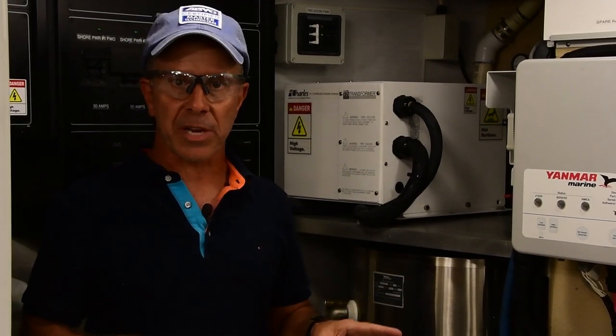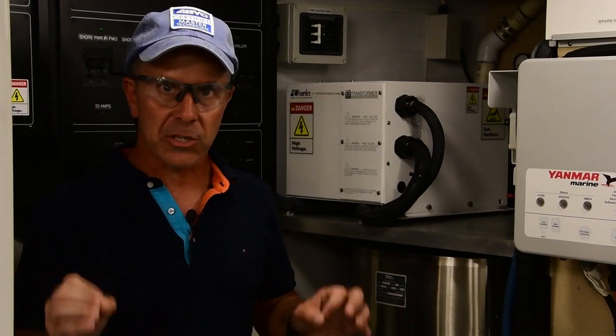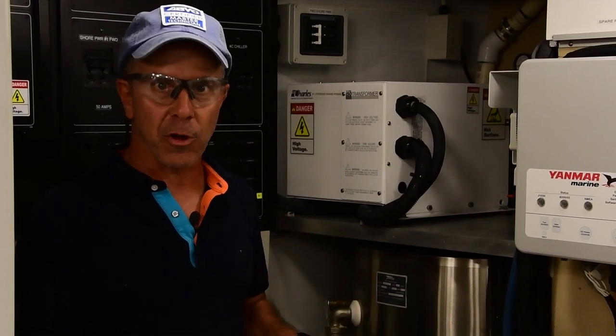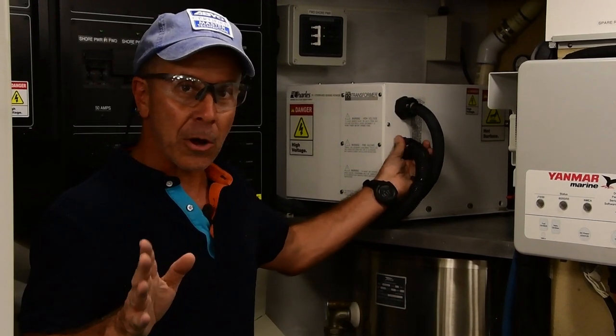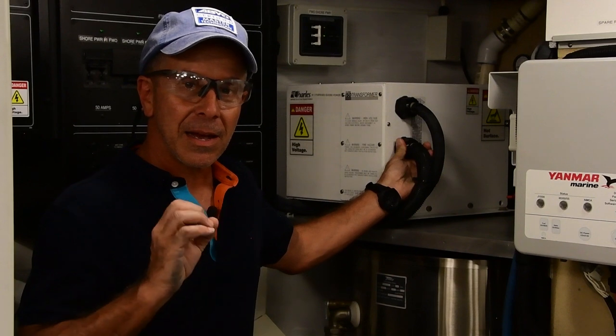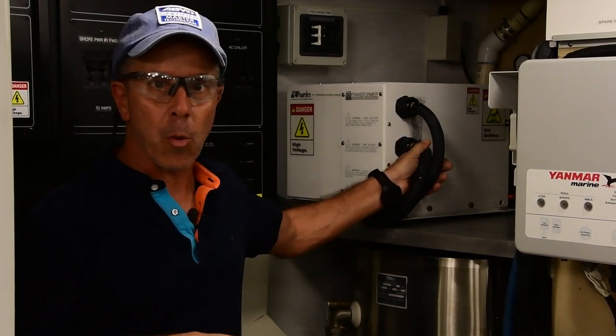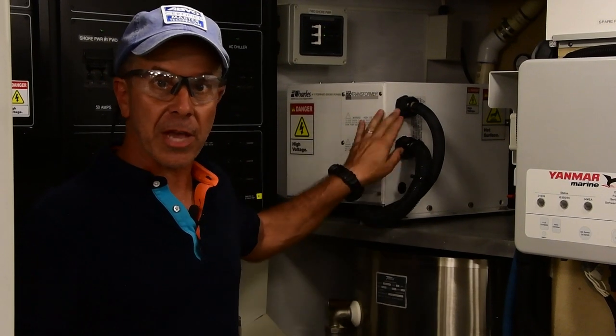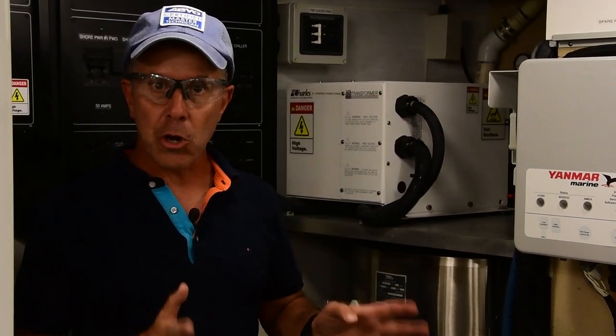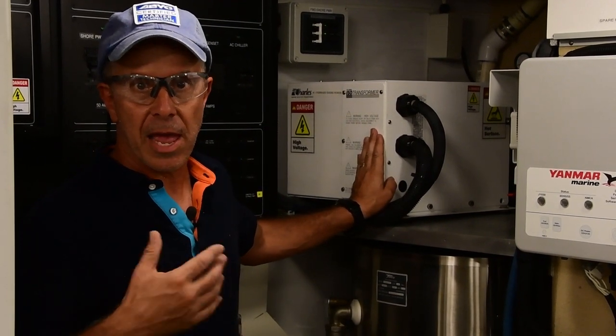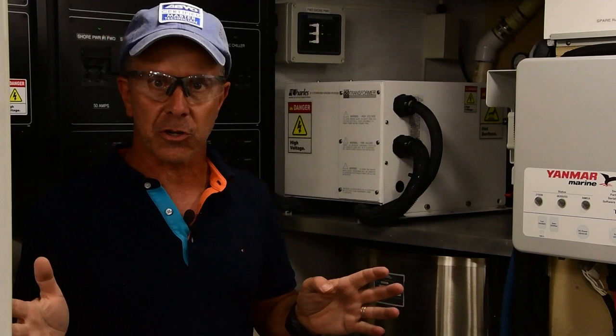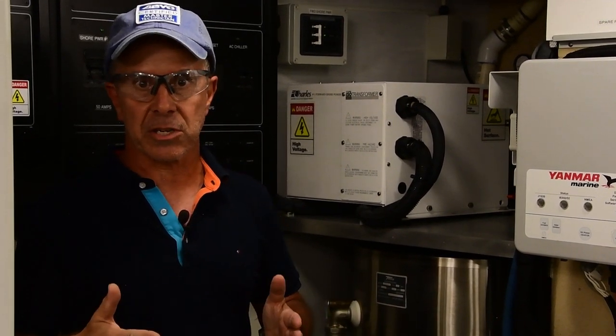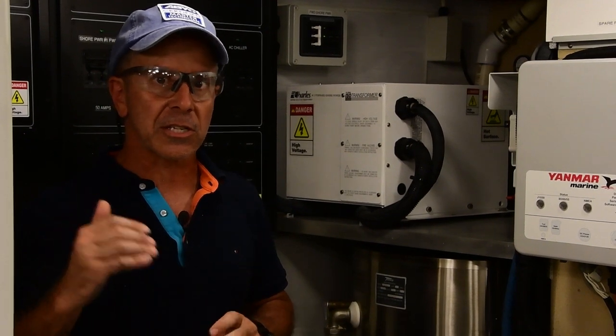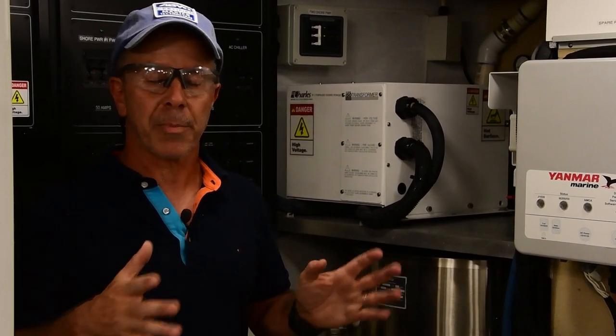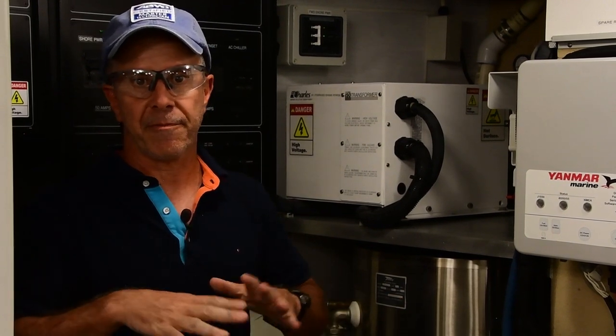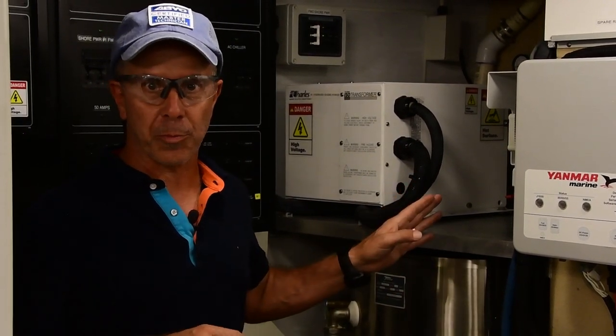American Boat and Yacht Council standards do provide for an isolation installation that is safe, provided all the instructions are followed, and among the most important being the cord grip and prevention for chafe, because if a wire can't chafe against this enclosure because that cord grip is there and it's installed properly, then there's no possibility of that case becoming energized and a potential electrocution hazard. So it's important to understand that that difference does exist between polarization and isolation, that there's that slightly elevated risk of electrocution. Personally, I believe it is minimal, provided the transformer is installed properly.